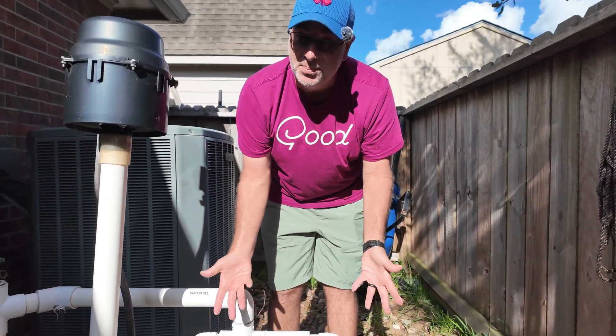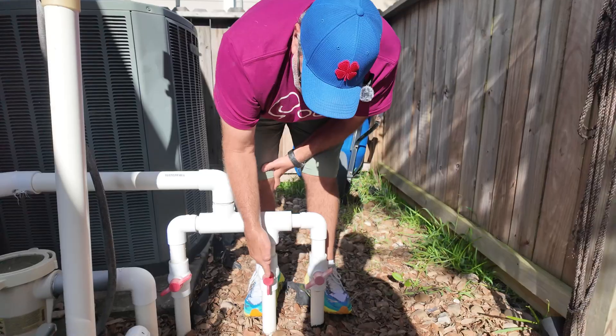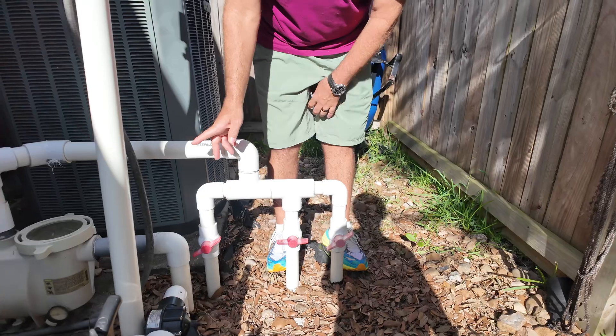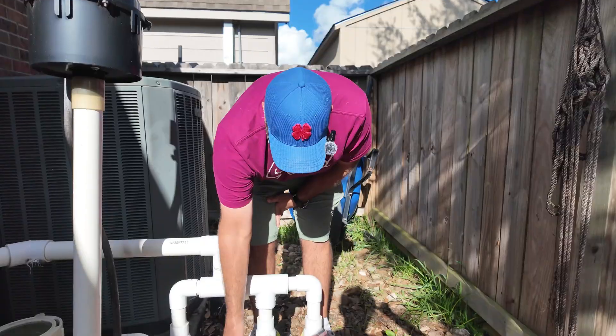That shows it's open; turn it perpendicular and it's closed. Pretty simple. When you're out in the field doing work, don't just start closing random valves. Walk out your line and look at different things, because if this is the discharge of a pump and you close it off, you're going to deadhead your pump. I've seen fires come off pumps, I've seen pumps spray out the side, I've seen seals blow — it can do a lot of harm. Don't ever close the valve 100% and expect the pump to be okay.